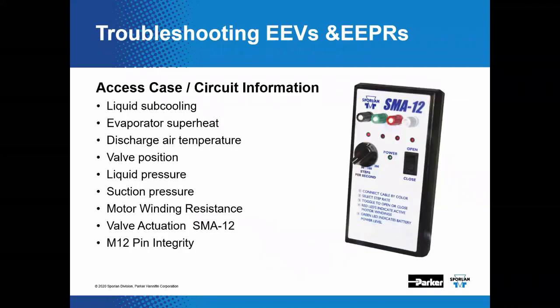I've got to say, if you plan to service any of our electrically actuated, electronically controlled valves, the SMA-12 is an invaluable tool to have at your disposal. It is a self-contained, compact step motor actuator. It acts like a little controller. It can be used to drive these valves, and it is an excellent troubleshooting aid.